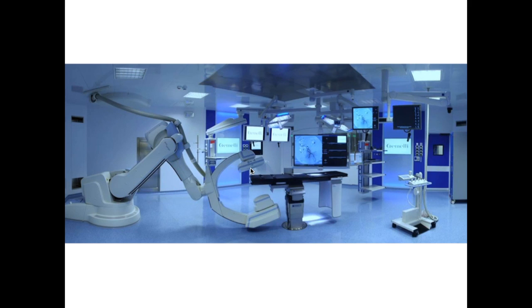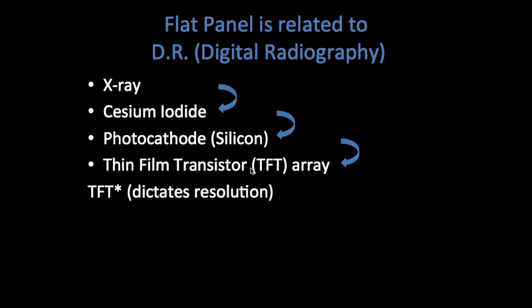The flat panel fluoroscopy system is related to digital radiography. The signal chain begins with the x-ray, then passes through cesium iodide — the same material used for the input phosphor in image intensifier systems. It is at this stage that x-ray photons are converted to light photons, and that conversion happens thanks to cesium iodide, which we still use in flat panel fluoroscopy.